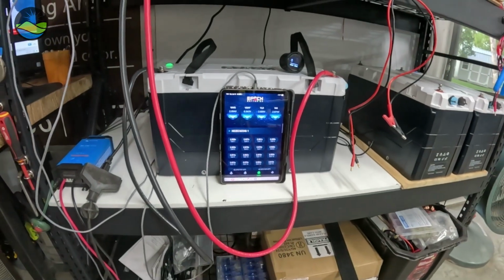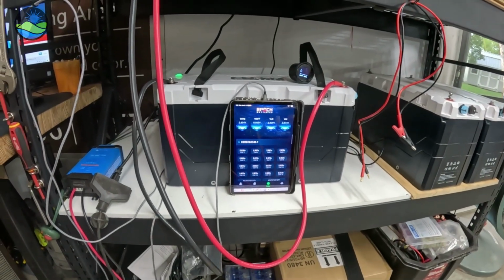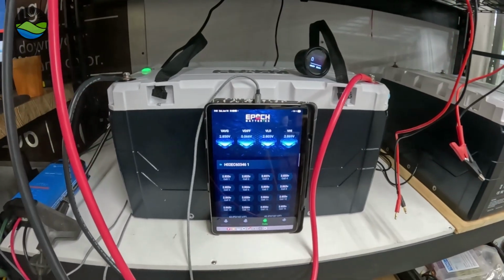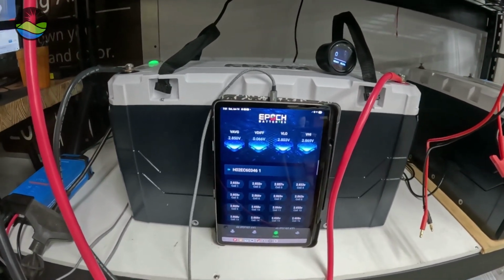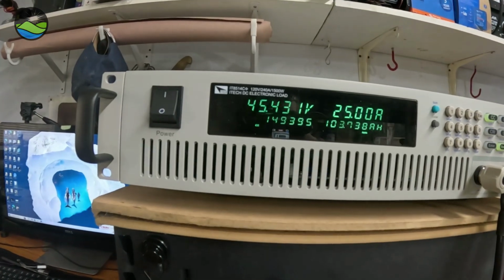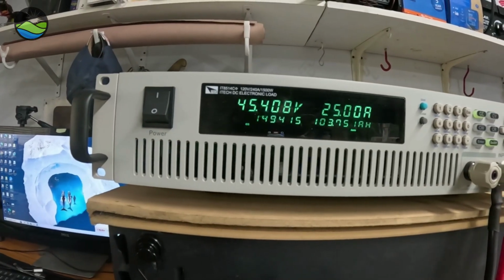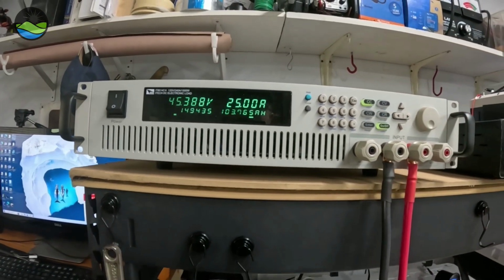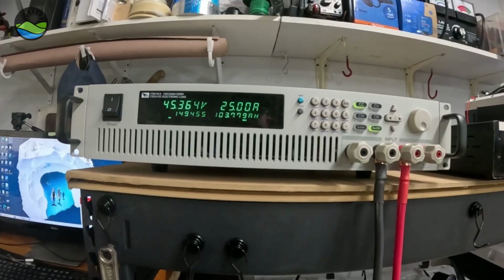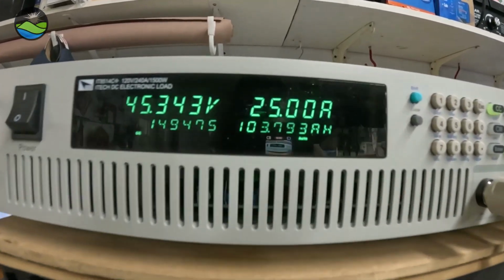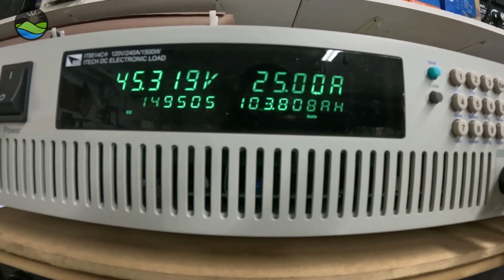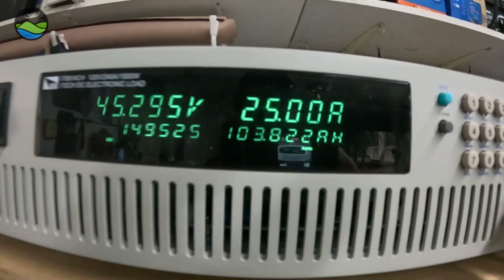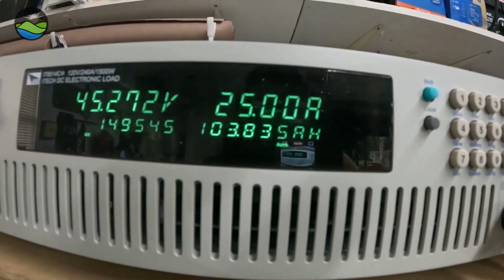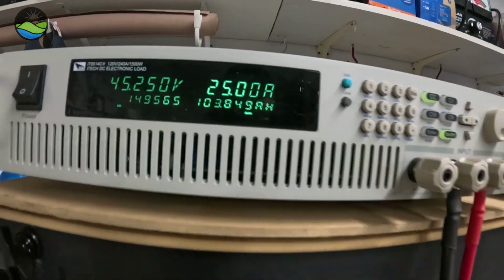Okay, so we're cap checking the Epoch 48 volt 100 amp hour battery. We're just about to the end of the test here. We're using the iTech 8514C Plus load tester. It's in cal, it's brand new, it's an expensive piece of equipment. Measures amp hours to 3 decimals. And we're pulling 25 amps, so this is a 0.25C load.